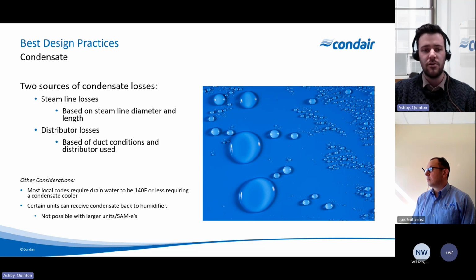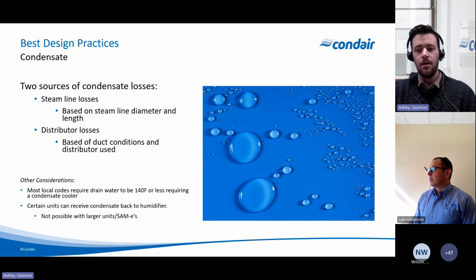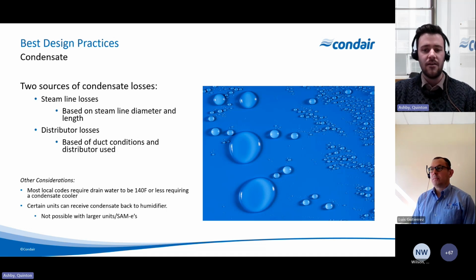So if you have a large distributor in an air handling unit and it's very cold in there, you're going to get more condensate. Why this is important is that it needs to be considered in terms of sizing. If you have, say, a 200-pound requirement in the space and you choose a 200-pound unit, you should know that you won't be able to get 200 pounds exactly out of the unit. There will be losses no matter what. We can try to minimize them as much as possible, but typically you will have to oversize a certain amount to get the steam that you want.